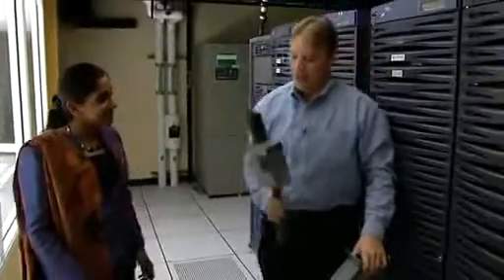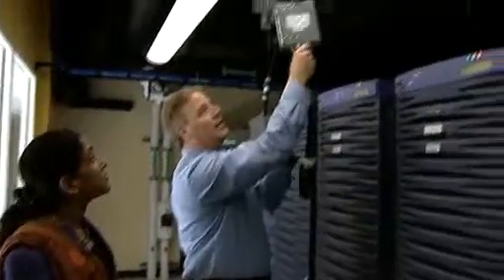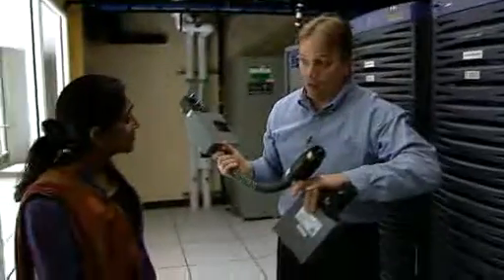So significant cost reductions when you really go back and say, how can I build my data center to be really efficient? Building data centers is expensive, but even changing power supplies into individual racks can have a price ticket of as high as $25,000. This is a 50 amp three-phase outlet, but now just think of it, it's just a module that I go into the busway and snap in. So literally in minutes, I can have the power where I need it to go.